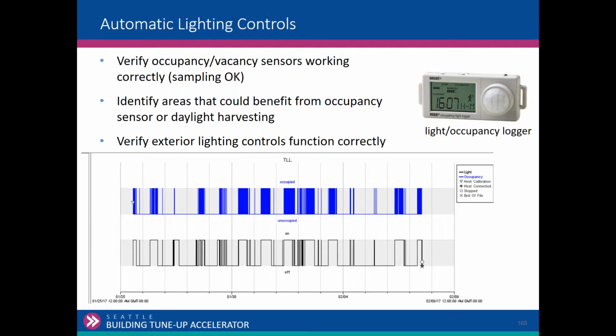I mentioned in our library we have these light occupancy loggers, and they're really unique in that they basically give you when it compares occupancy to the lights being on. So we can see here that the lights being on track occupancy. That's what we want to see. If the lights stayed on the whole time, even though the occupancy varied, then we'd have a problem. Our occupancy sensor isn't working correctly. So there's ways that we can verify and log whether or not. And obviously in a large building, you may have 100 occupancy sensors, 500 occupancy sensors. Sampling's okay. Look at how many, spot check those, and see if they're working correctly.